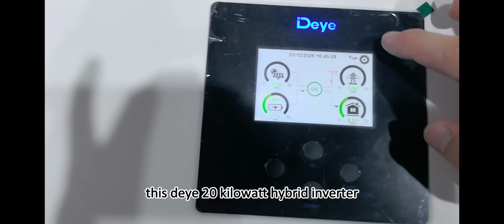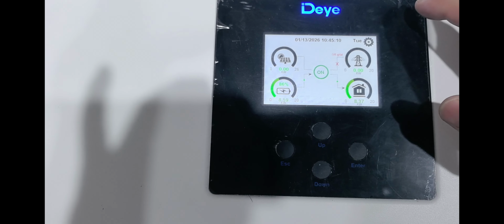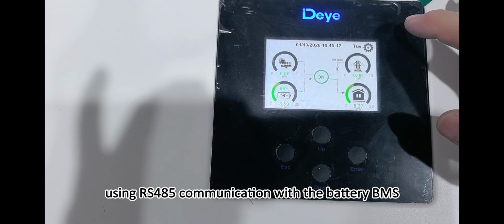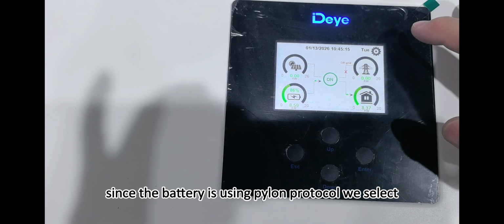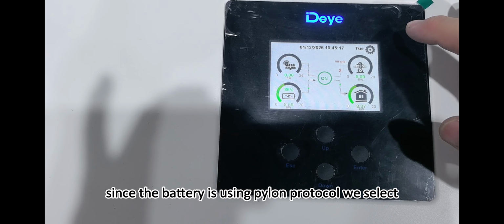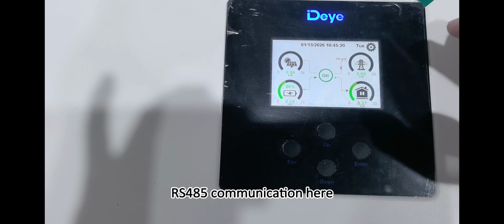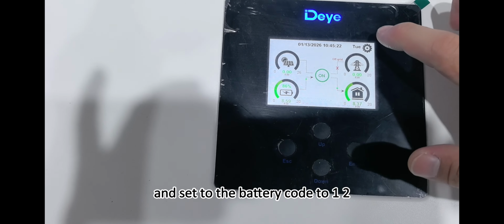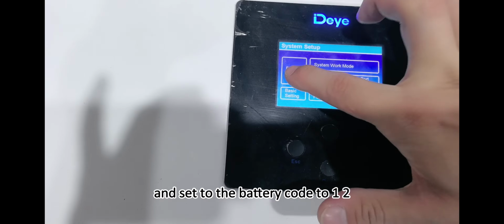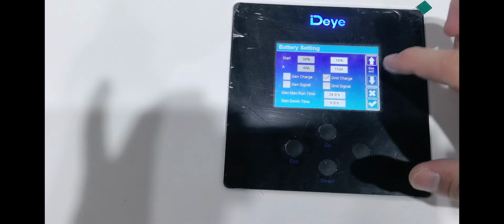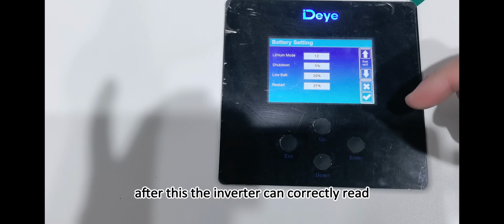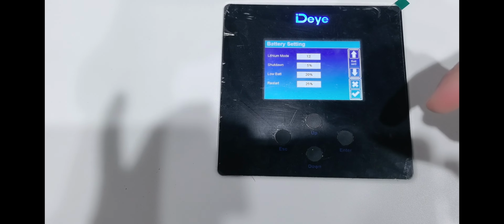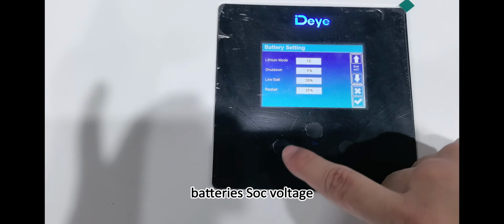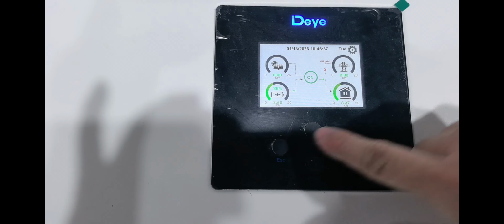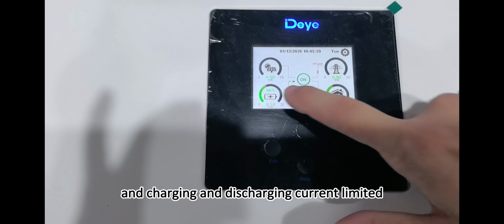the charging and discharge. This is the 20kW hybrid inverter using RS485 communication with the battery BMS. Since the battery is using Pylon protocol, we select RS485 communication here and set the battery code to 1, 2. After this, the inverter can correctly read battery's SOC, voltage, and charging and discharging current limit.